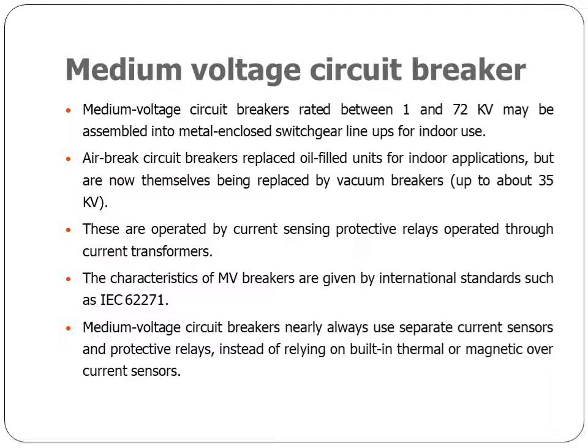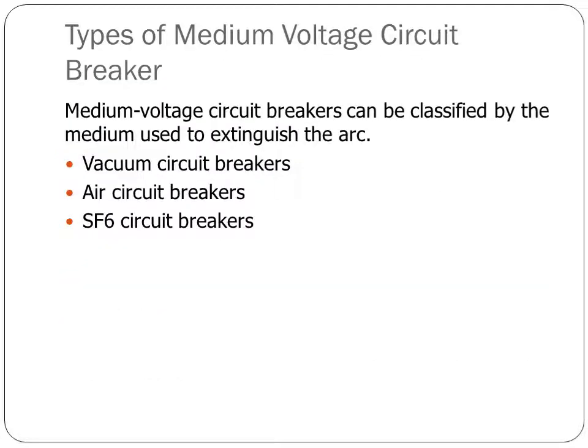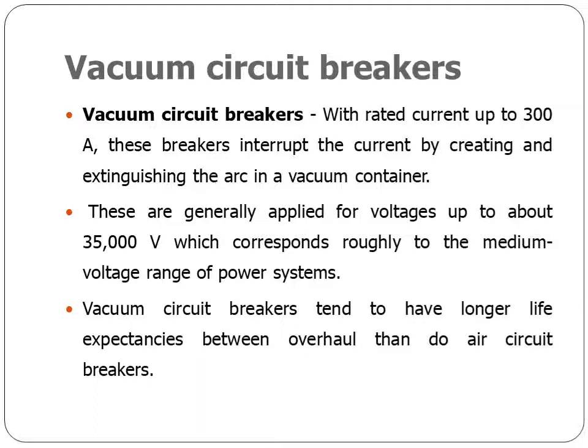The characteristics of medium voltage breakers are given by international standards such as IEC 62271. Medium voltage circuit breakers nearly always use separate current sensors and protective relays instead of relying on built-in thermal or magnetic overcurrent sensors. The types of medium voltage circuit breakers are classified by the medium: vacuum circuit breaker, air circuit breaker, and SF6 circuit breaker.